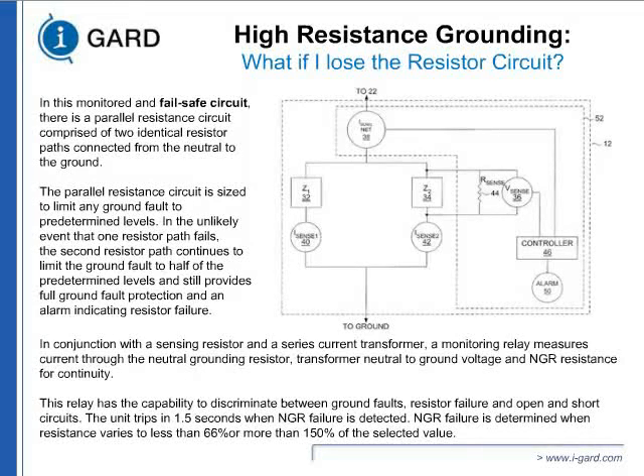You can have a sophisticated system where you have a disconnect. Some of our sites have that, where we can disconnect that faulty resistor and try to put a new one in there without shutting down the system. You can still see the incentive is the same, process continuity. Now high resistance grounding allowed us process continuity to do it safely. That objective has not changed, to keep the electricity going so we can have some process continuity in there.